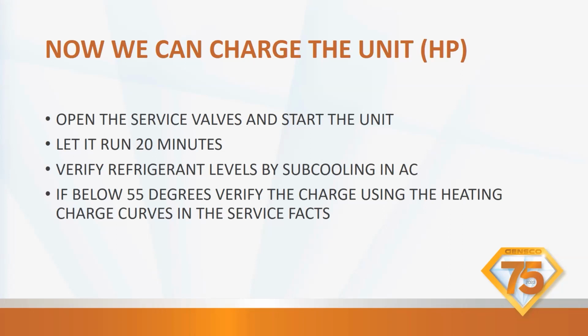Okay, so the charging charts go down to 55 degrees. That's why we can charge down to 55 degrees in cooling mode. Now it's not as accurate as if you wait till 65, but you can charge down to 55 degrees because we have charts that match that. If you have a chart in your install guide or your service facts that goes down to 65, go to 65. If it goes to 55, go to 55. Whichever they can make charts for.